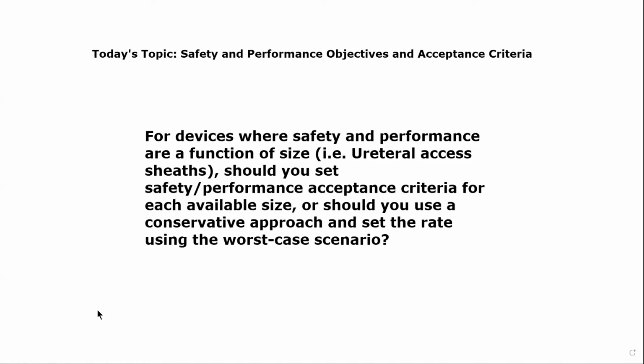In that case, what we've done in the past is we set the overall acceptance criteria. So we say that if we pooled all of these data together, we can get a range of technical success anywhere from 90% to 99%. If we separate it out, maybe the smaller ones have a lower range than the larger ones. In that case, we would also present the performance criteria broken down by size or groupings, because that would give the notified body a sense that you have your overall range, but you also are acknowledging that one size may confer more challenges in that particular technique than another size.